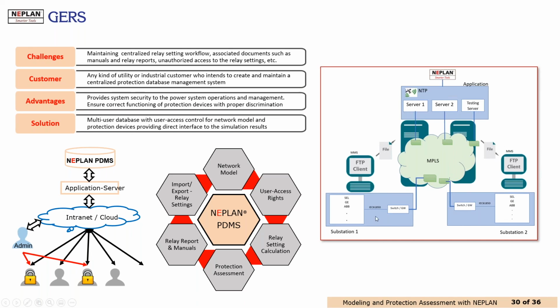The IEC standard 61850 allows to send the settings using the MMS protocol that is more related to the state of the relay. The FTP standard, file transfer protocol, is typical also, and that is highly used to get the current condition of the relays. So since we have this kind of protocols to get the information from the relays, this information comes to the external server, maybe to the SCADA server, where it is easily connected to NEPLAN using the web services. Remember, we can connect any functionality on NEPLAN to any external application like the SCADA using that layer of the web services. So this is the architecture that we suggest for the integration in real time about the current conditions of the relays.